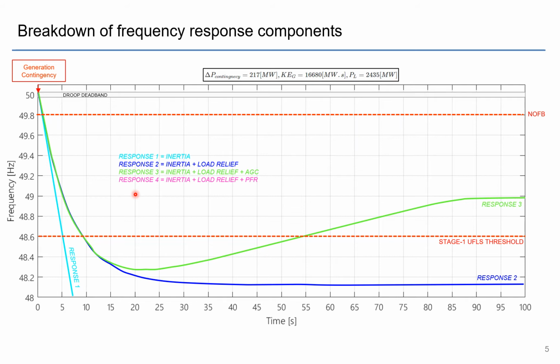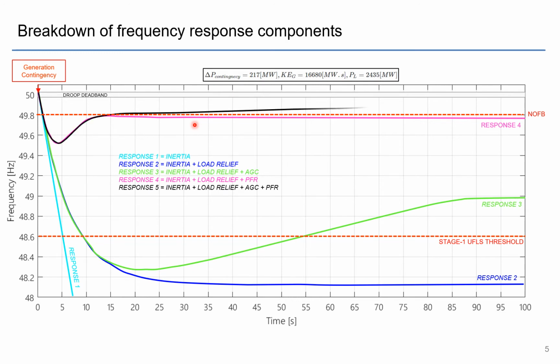So if we had inertia and some load relief and now the primary frequency response, so just the generator droop, this is where we start seeing some better frequency responses. And here we see that the frequency response is limited to a reasonable nadir. However, it settles at a frequency that is below the normal operating frequency band, the NOFB. So what we really need is all of the different components put together, and that brings you back towards 50 hertz and the droop dead band.